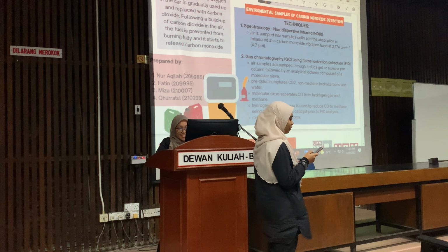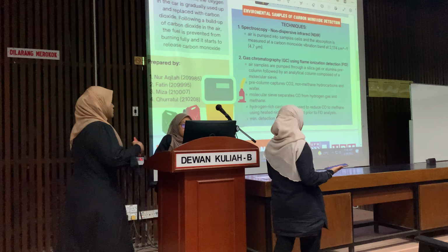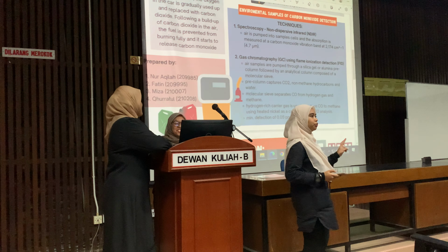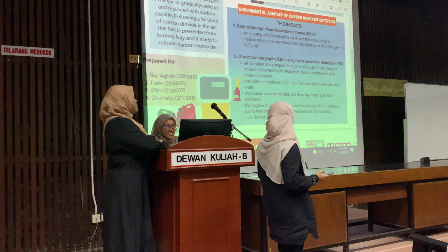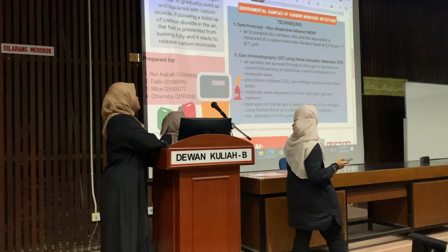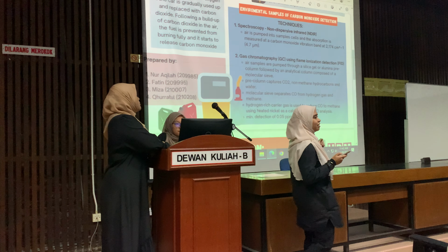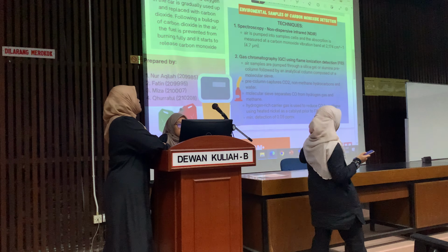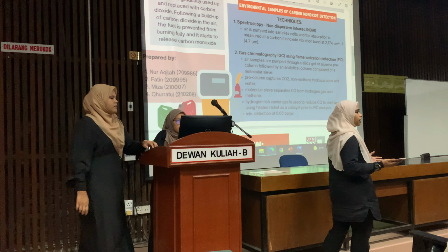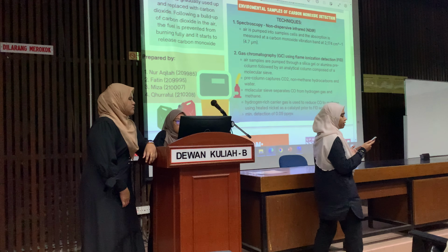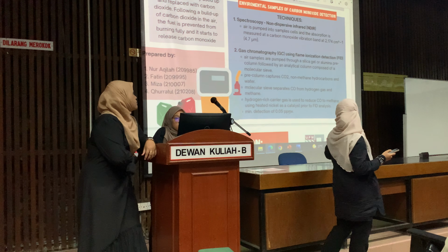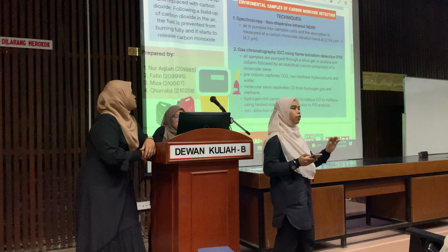Okay. Now, how can we determine the presence of carbon monoxide in an enclosed environment? There are two types of technique to detect carbon monoxide. The first is spectroscopy, which is non-dispersive infrared, NDIR. In this method, the air sample flows into the machine, and from that we can see a vibration band at a certain micrometer that shows the presence of carbon monoxide.